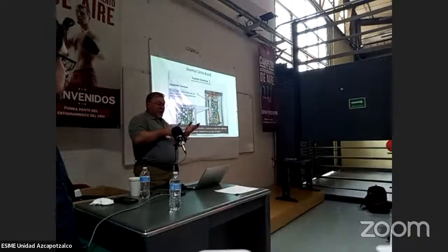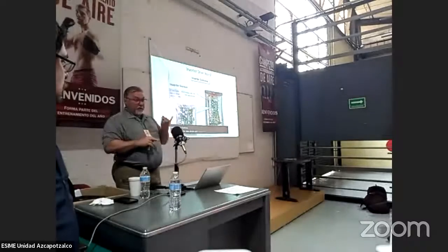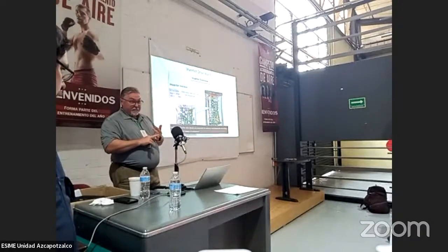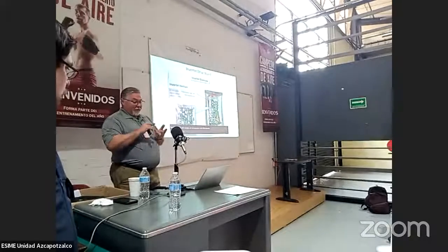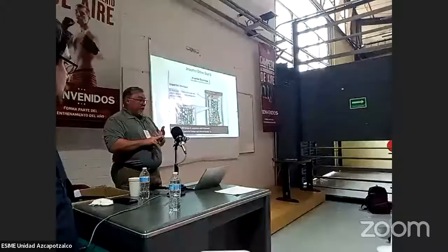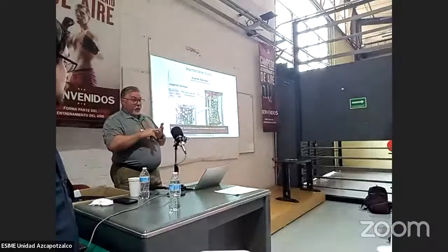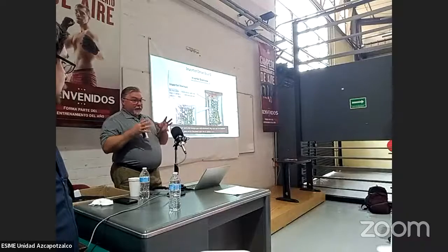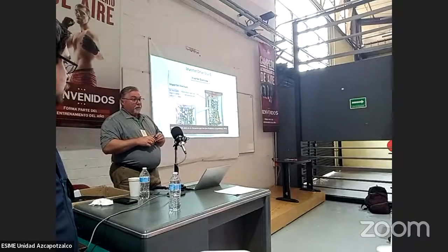The only time I've seen the compressor at the start throwing that code, most of the time the compressor is locked up. I've seen most of the time it's locked up. I've very rarely seen the board bad. I have seen it, but it's not often that I see the board as the problem. It's typically going to be the compressor.